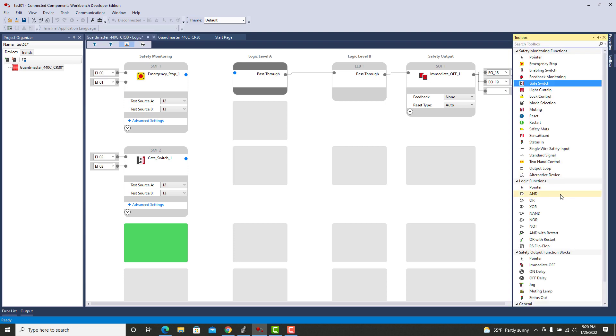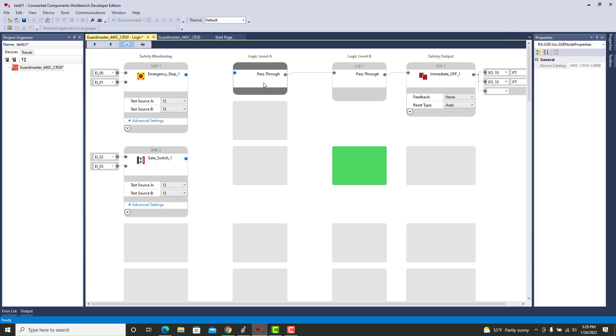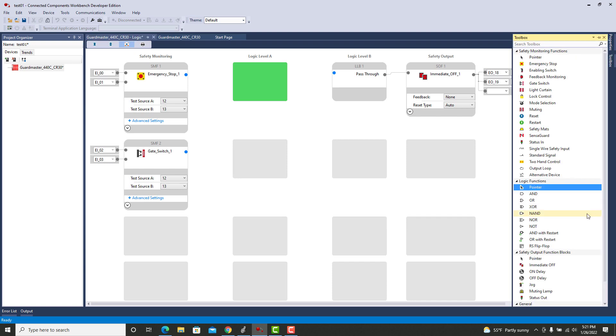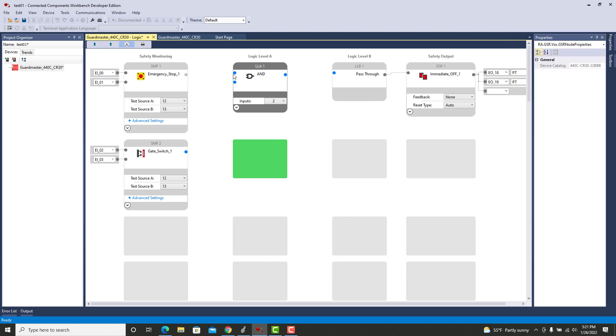I'm going to take and select that connection and delete it. So now these went back to blue dots. I'll try just to convert it, I don't know if it'll let me do that or not. I'm going to go down here and make it an AND. See, it won't let me do it, so I'm going to have to delete this connection. Then select this, go to toolbox and select AND. I can drag it over here or just double click and it pops it in there. Now I can connect the e-stop output to that input on the AND, and this one to this one, and then I can connect this back up. We're back in good shape now.